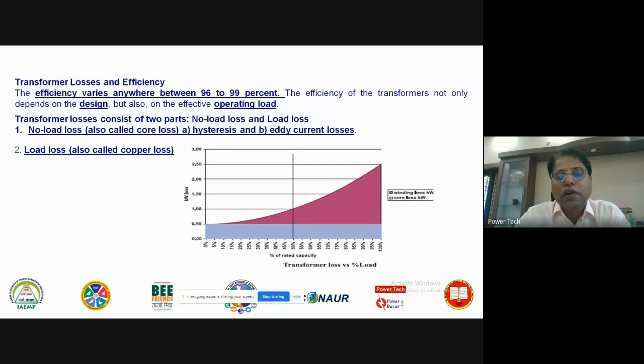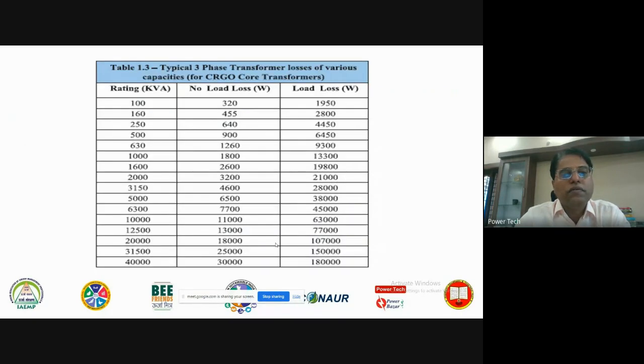And this is the transformer loss curve vis-a-vis load. And you know, efficiency of a transformer is in the range of 96 to 99%, and the optimal load for a conventional transformer is 70%. That means there are losses, maybe 1 to 4%. It is very minimal if you see, but if you see the number of transformers and the MVA capacity, if you can reduce these losses a little bit by improvement of design or technologies, definitely we will achieve a lot of energy conservation and efficiency in our electricity or distribution business.